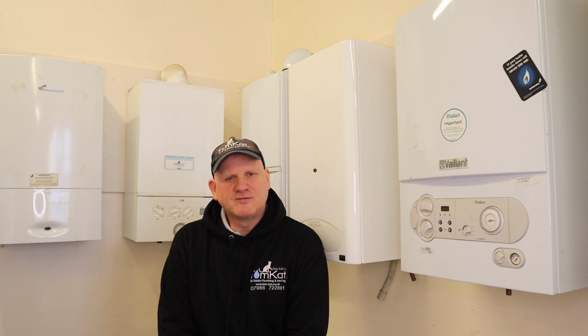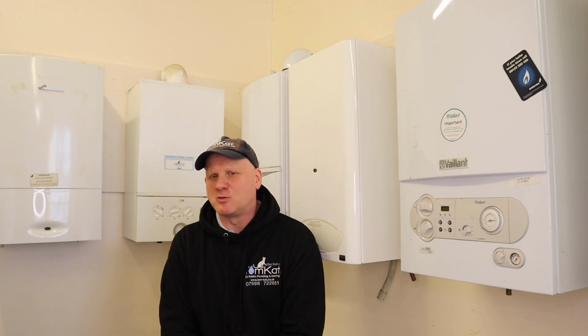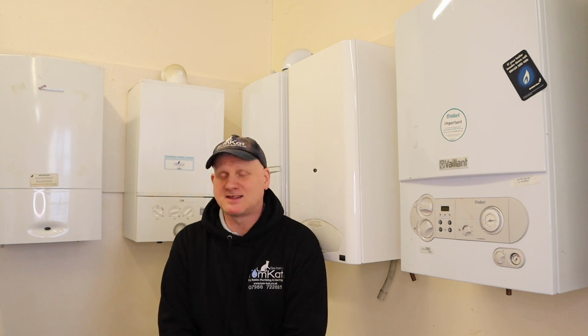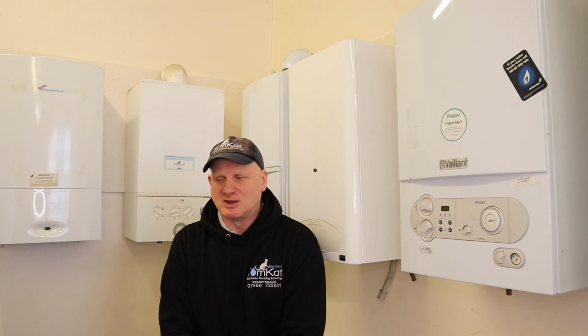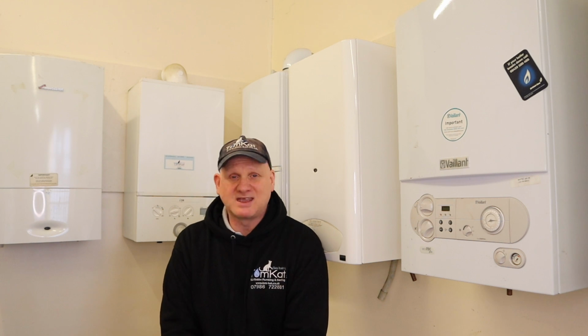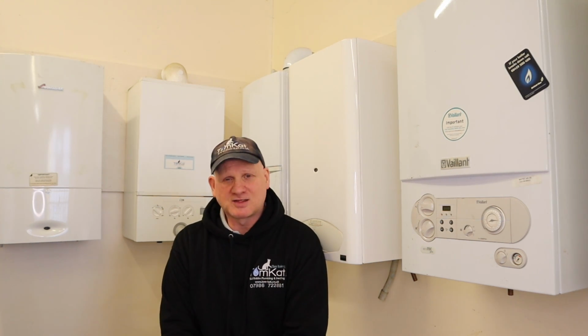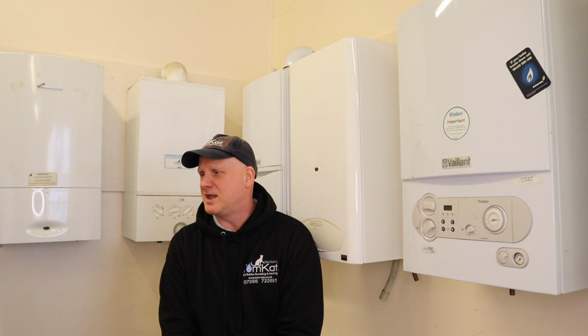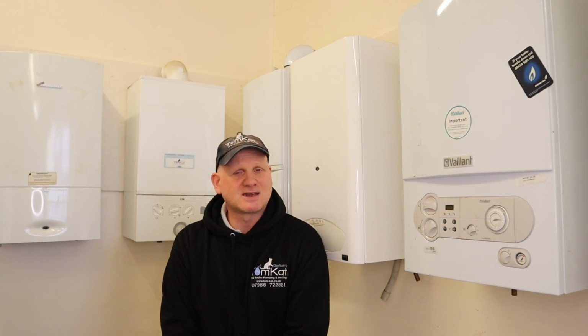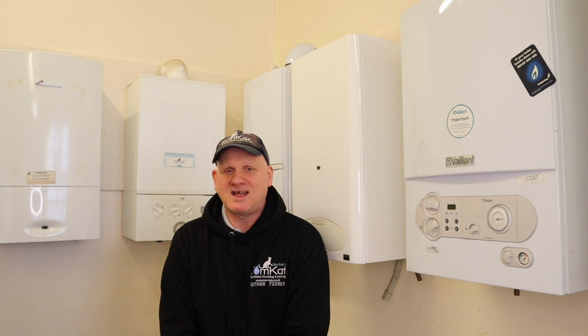Now again, with stainless steel we don't really need to worry about inhibitor levels for the heat exchanger itself, but we do for the system. But with an aluminium heat exchanger, we need to make sure we keep on top of our pH levels. Also, if we don't keep on top of limescale if you're in a hard water area, and sludge, magnetite, no matter what heat exchanger is installed in a boiler or what boiler you install, it won't make any difference because it won't last very long. Also, if boilers aren't serviced every 12 months, pH levels aren't monitored and magnetic filters aren't cleaned, then how can you expect a boiler to last very long?